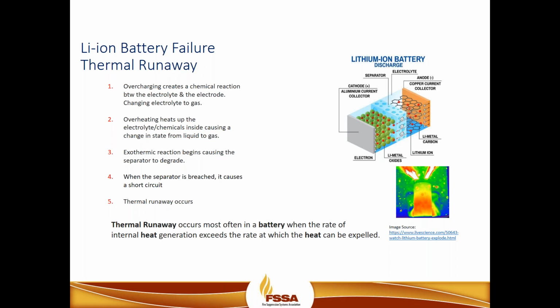From an overcharging event, I think it's a little bit of a misnomer that if you achieve overcharging, that you'll also have elevated thermal levels as well. And of course, this is not the case. In many cases, overcharging happens at a relatively low temperature, and we'll touch on that later on in the presentation. But once thermal runaway is achieved, that is an exothermic reaction, and it really cannot be prevented. It will create its own oxygen and its own fuel, and the only way really for it to be put out is for it to burn itself out.